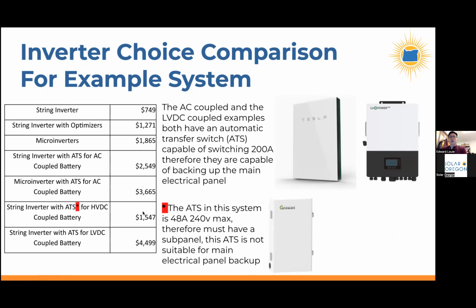One of the things that is absolutely necessary in a system with batteries, where you desire that system to continue to power your house during a blackout, is to ensure that the house does not send electricity back to the grid and potentially electrocute line workers that are trying to restore power. And so it's absolutely necessary to have an automatic transfer switch to disconnect the house and island the house so that the energy to power the house stays within the house during a blackout. And if you were to do that and be able to island the entire house, then you need a transfer switch that's capable of switching 200 amps, because that is the size of a main service panel, a main circuit breaker panel in your house. And the Tesla gateway is capable of doing that.